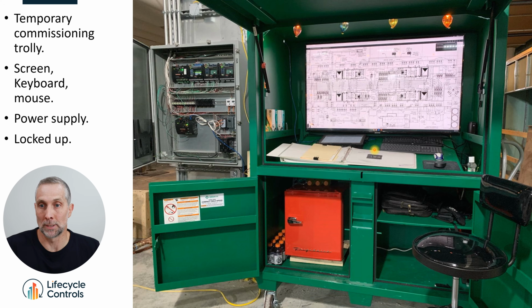AHU1, you commission the inputs and outputs, get the graphic online, the trends built, the alarms built, all mapped through, the time schedules, everything. Move across to AHU2, AHU1 goes offline, AHU2 comes online. You just work through the whole thing. You're not just doing point-to-point commissioning. You're doing all of the commissioning, bang, in one shot.